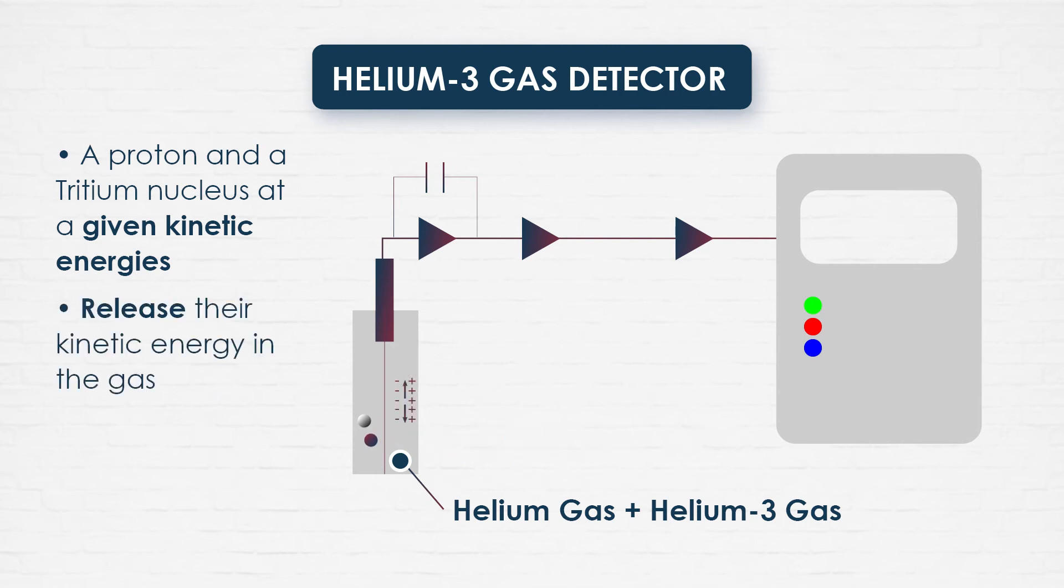Once emitted, the two products release their kinetic energy in the gas. The result is the ionization of the gas with a consequent generation of a certain amount of charge. The charge is finally collected by the electric field to create an electric signal that can be counted.